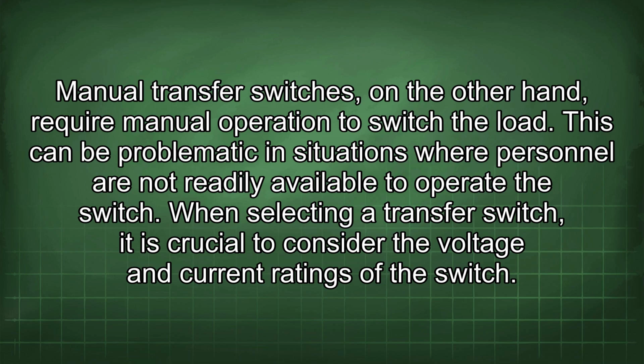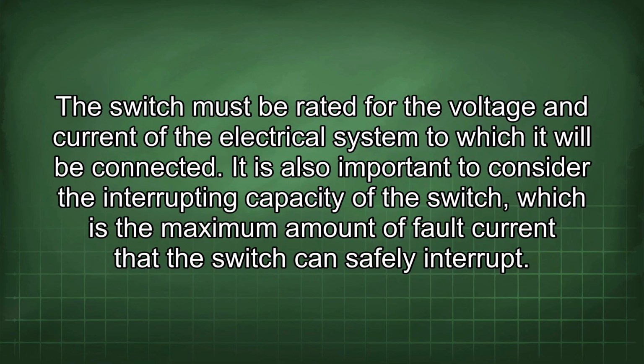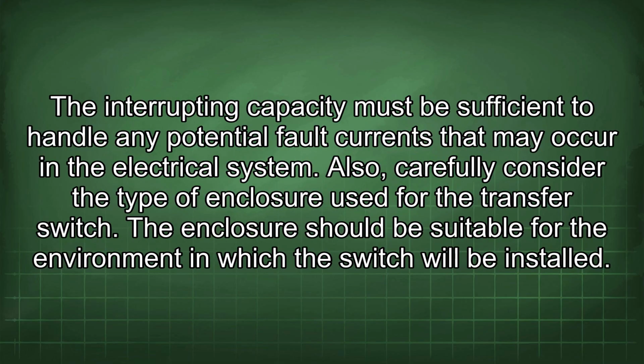When selecting a transfer switch, it is crucial to consider the voltage and current ratings of the switch. The switch must be rated for the voltage and current of the electrical system to which it will be connected. It is also important to consider the interrupting capacity of the switch, which is the maximum amount of fault current that the switch can safely interrupt. The interrupting capacity must be sufficient to handle any potential fault currents that may occur in the electrical system.